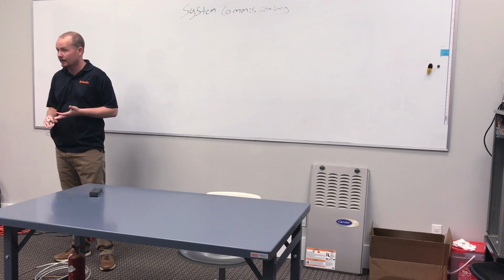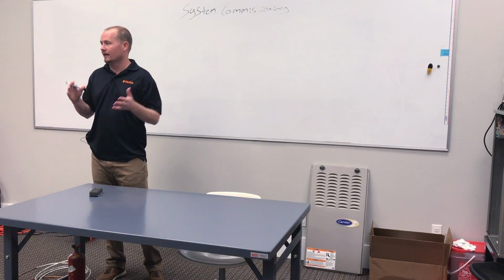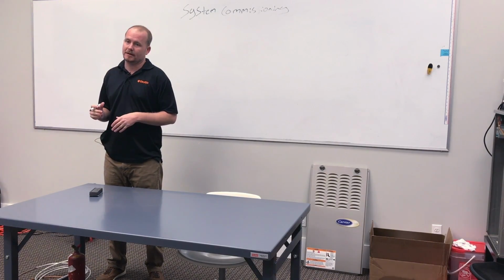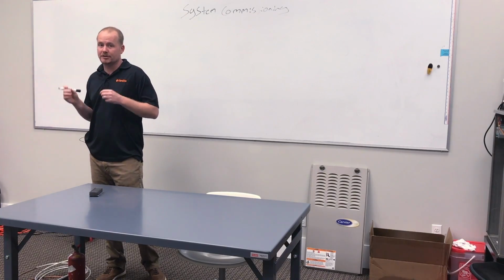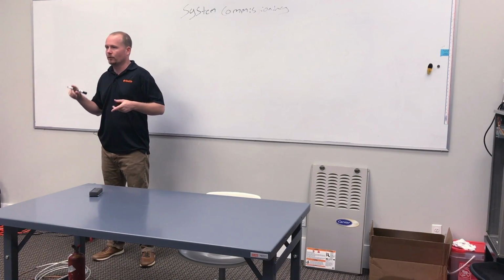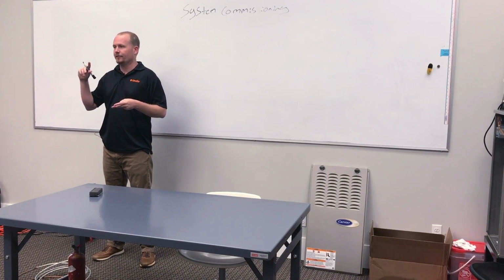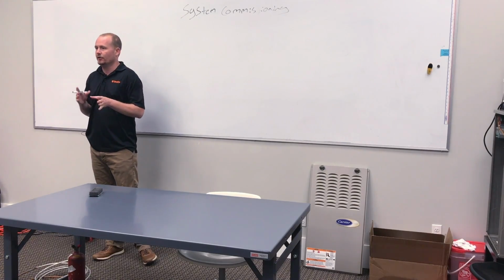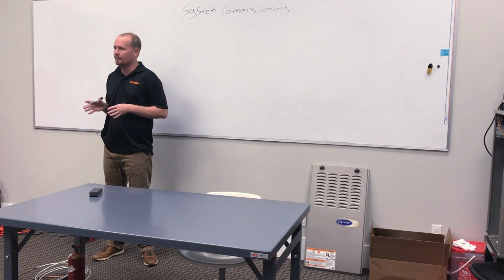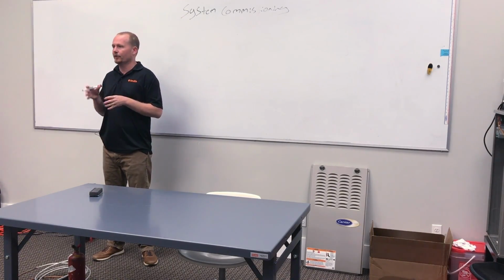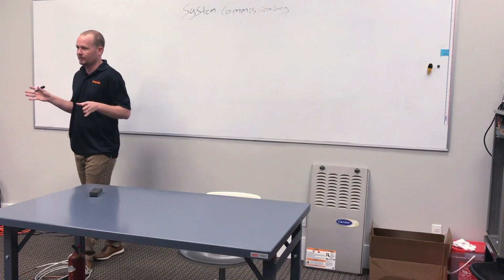Recently we did a TXV. You install a new blower motor. You do anything that's really critical to the system's operation, you need to do a full system commissioning, which is different than, say, if you cleaned a drain line or did a maintenance or changed a capacitor or a thermostat. Now you have to test everything that's pertinent to that repair, but you're not necessarily going to go through soup to nuts and make sure that the system is fully commissioned.